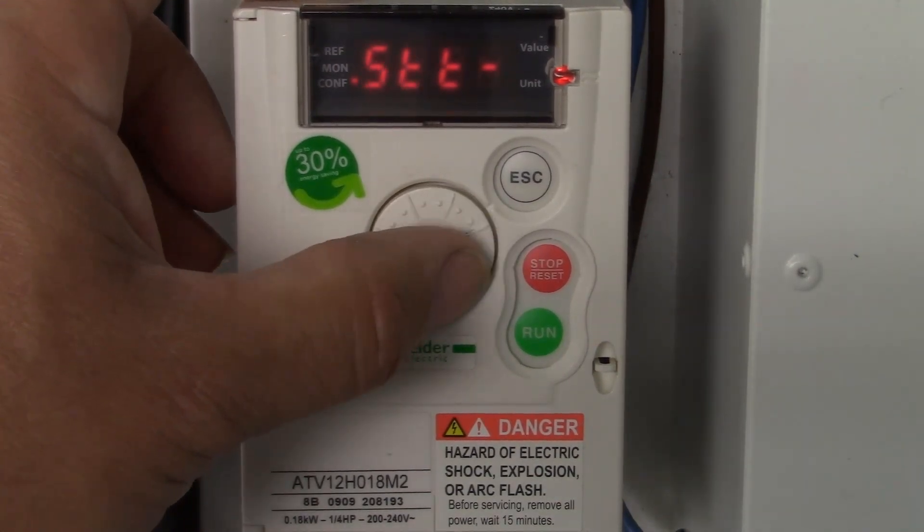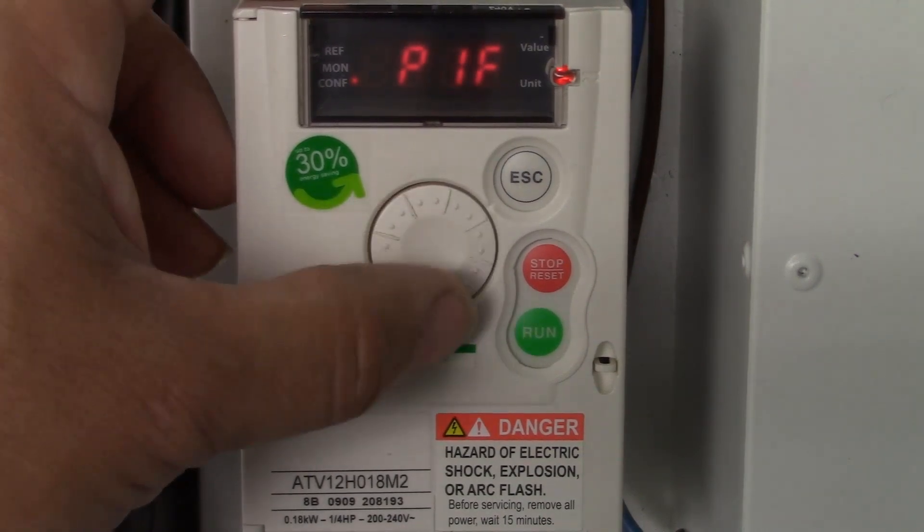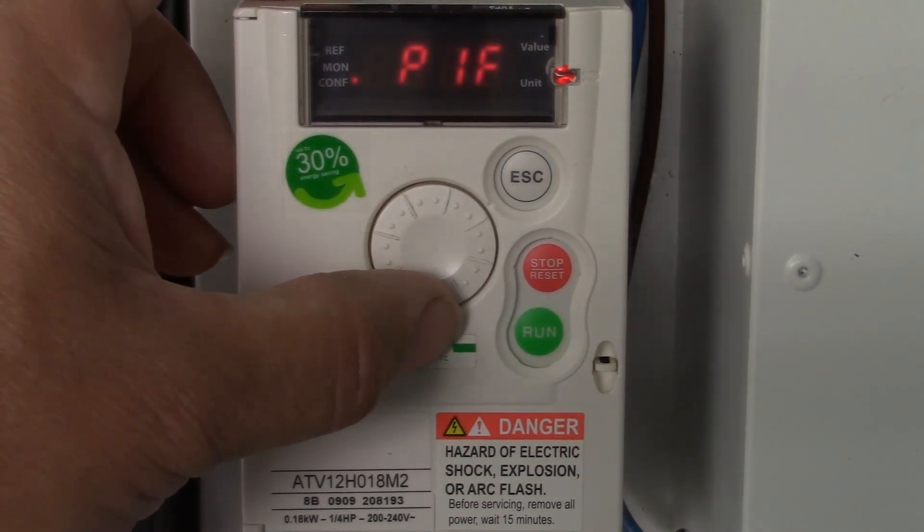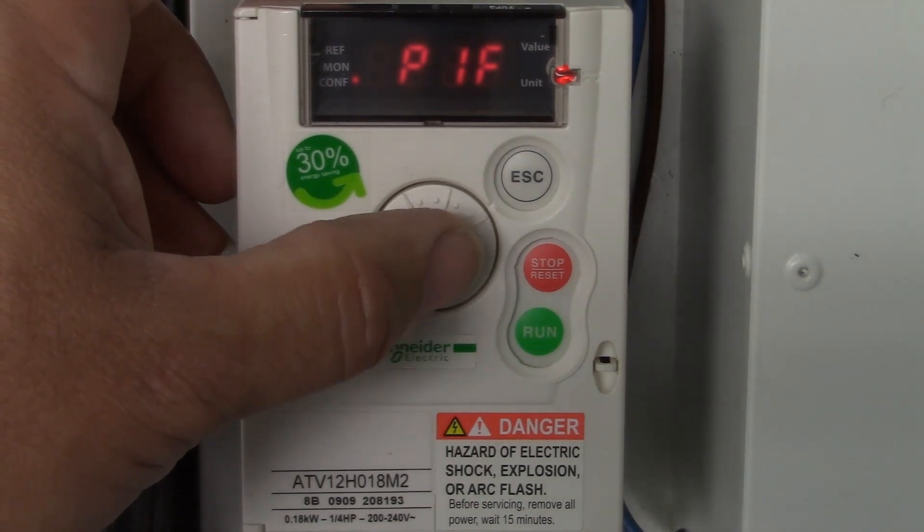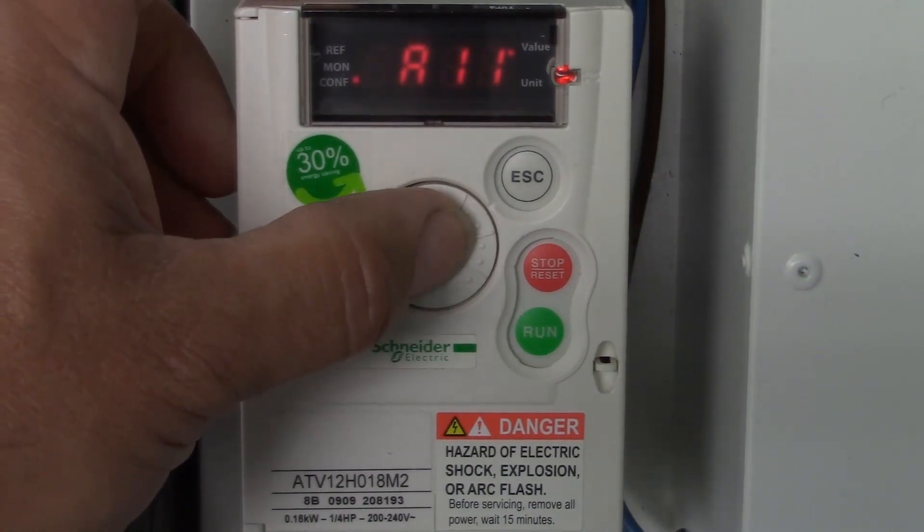Now scroll down to the PID menu and press enter. You will now have PIF on the display. Press enter and select the input to be used for the feedback. In this case AI1 as it is the only analog input on this drive.